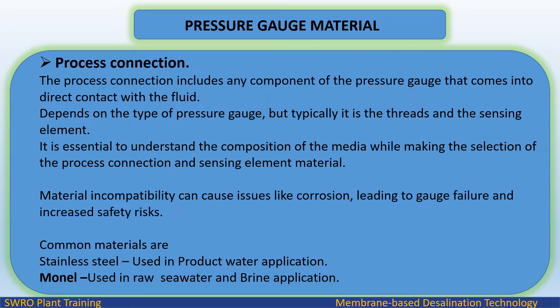Process connection: The process connection includes any component of the pressure gauge that comes into direct contact with the fluid — typically the threads and the sensing element. It is essential to understand the composition of the media when selecting the process connection and sensing element material, as material incompatibility can cause corrosion, leading to gauge failure and increased safety risks. Common materials are stainless steel, used in product water applications, and Monel, used in raw seawater and brine applications.